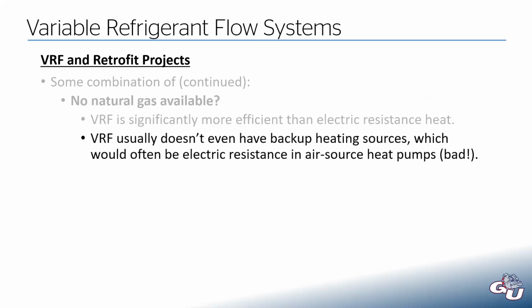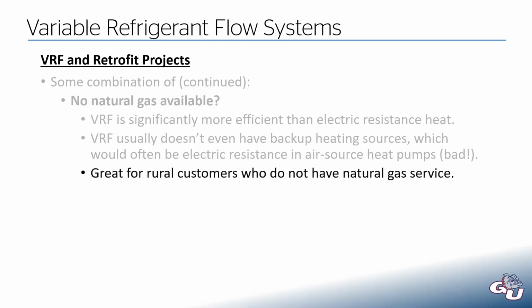Additionally, VRF usually doesn't require any backup heating sources. A lot of times, we talked about this last time, these air source heat pumps require a backup heating source for when it gets very cold and they don't run very well. VRF systems are built with more robust heat exchangers, and they get much better performance in those low outside air conditions. The same physics apply. The output and the COP do get worse as it gets colder outside, but it doesn't derate nearly as badly as a traditional heat pump system. So this is really a great system type for any rural customers who don't have natural gas service.